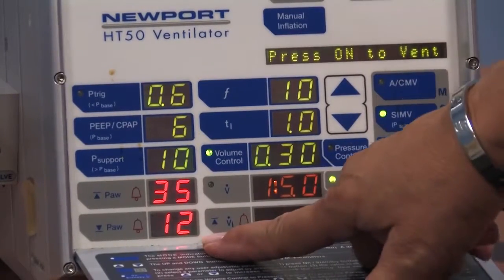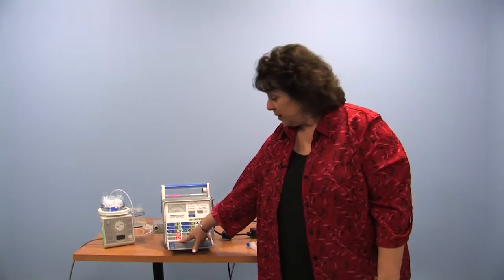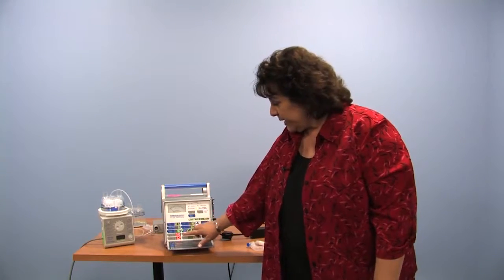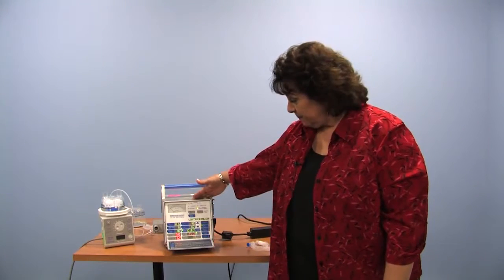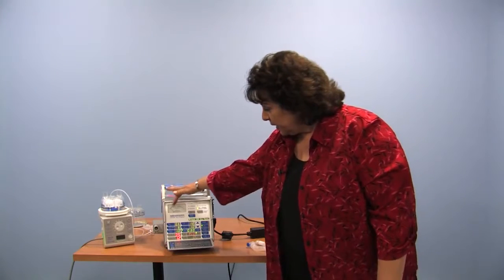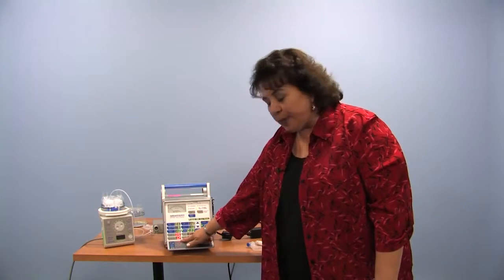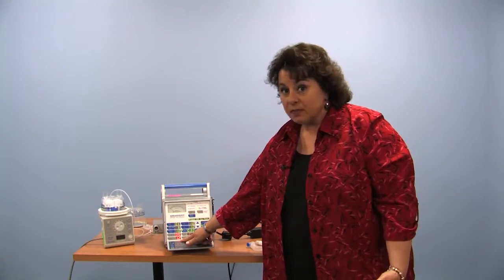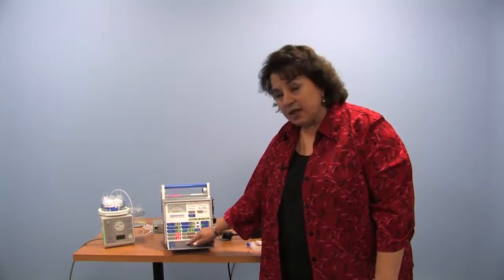We also see a low pressure alarm, typically utilized for disconnect, for example. This is set at 12 centimeters of water. So right now, our patient here, the needle should go up to 16 and down to 6, up to 16 and down to 6. So if it doesn't go past 12 because of a leak, the machine will tell us. And if it does go past 35 because they coughed, for example, it will tell us.